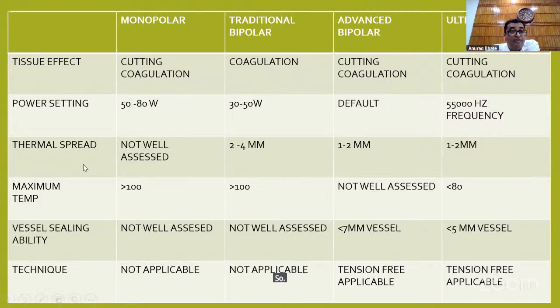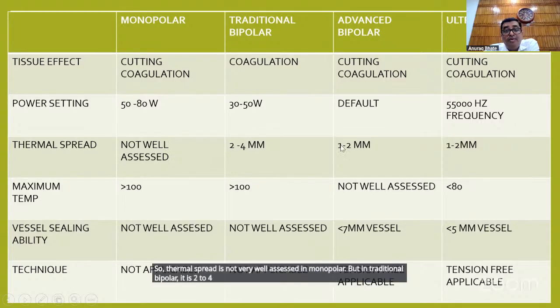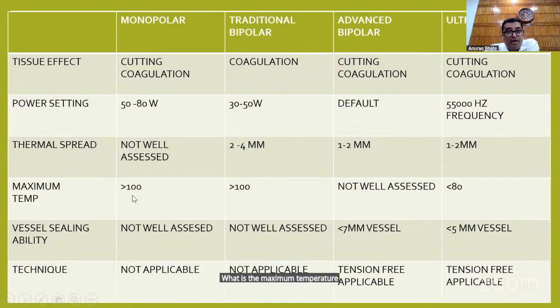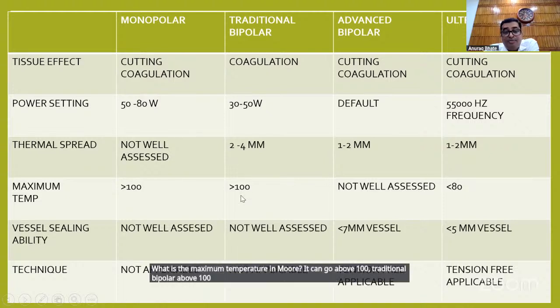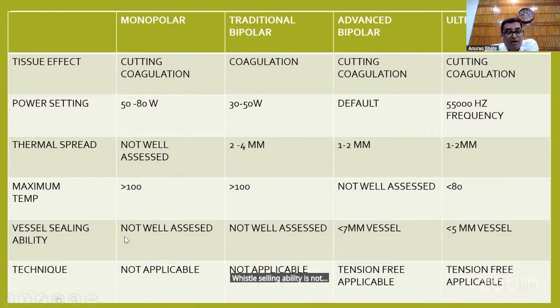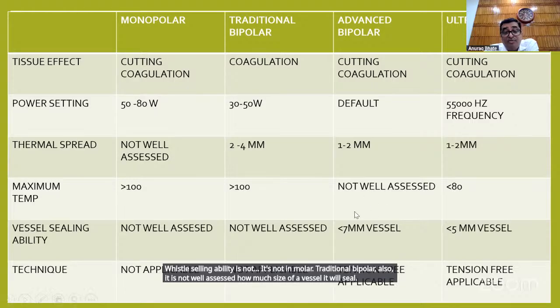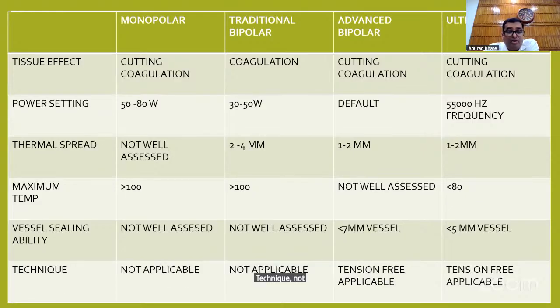So thermal spread is not very well assessed in monopolar, but in traditional bipolar, it is 2 to 4 mm, 1 to 2 mm in advanced bipolar, and 1 to 2 mm in ultrasound. What is the maximum temperature in monopolar? It can go above 100, traditional bipolar above 100. Advanced bipolar systems which are presently used, you cannot really well assess, but in ultrasound it is less than 80 degree. Vessel sealing ability is not there in monopolar. Traditional bipolar also, it is not well assessed how much size of vessel it will seal. Advanced bipolar, yes, it is less than 7 millimeter, and ultrasound is less than 5 millimeter. Technique, not applicable for monopolar. The rest are tension-free applicable.